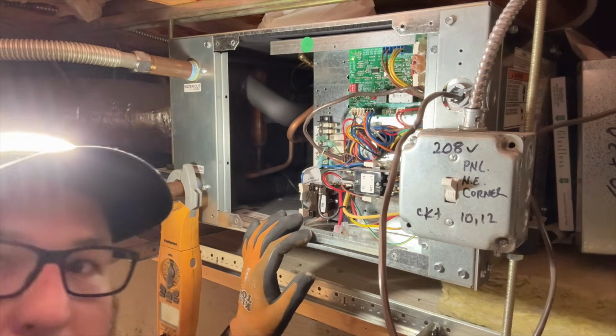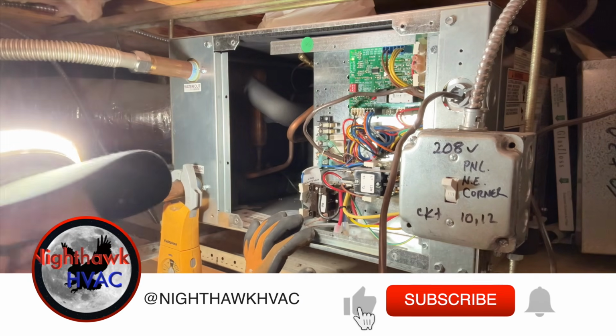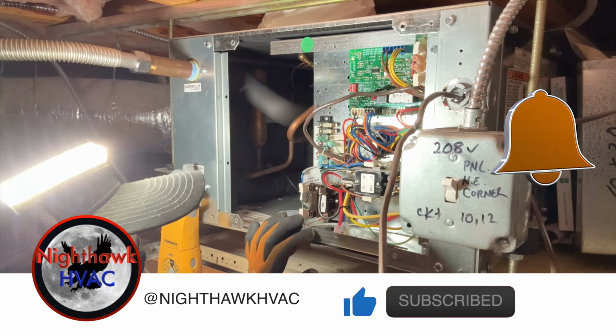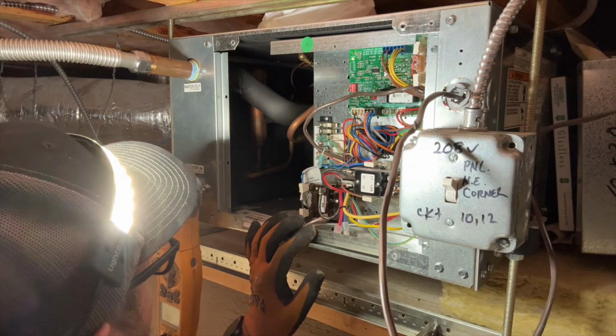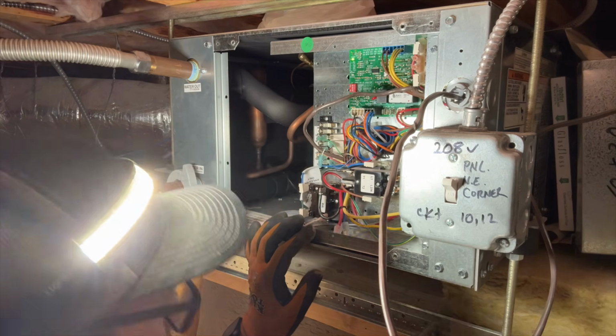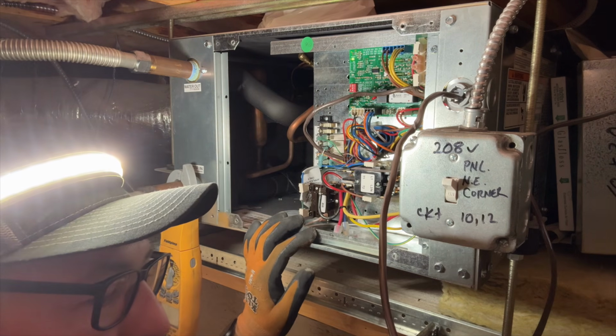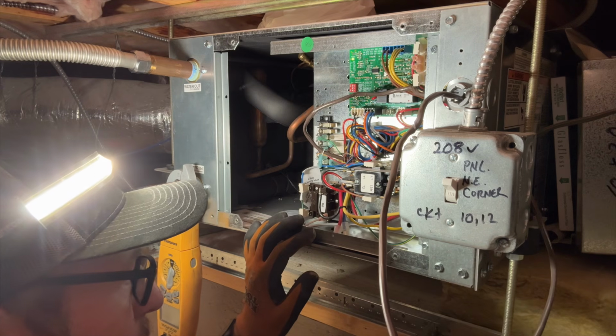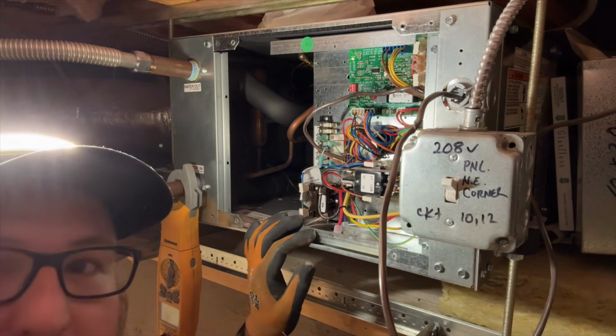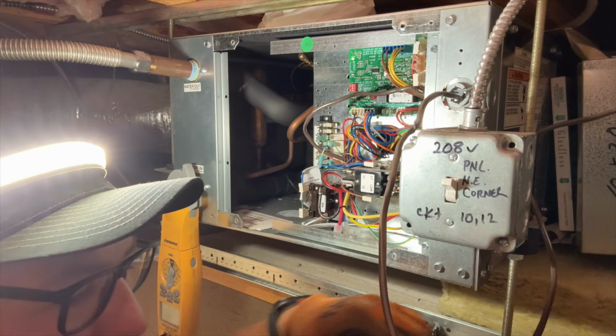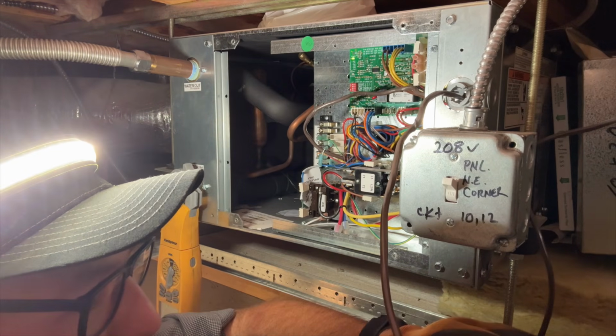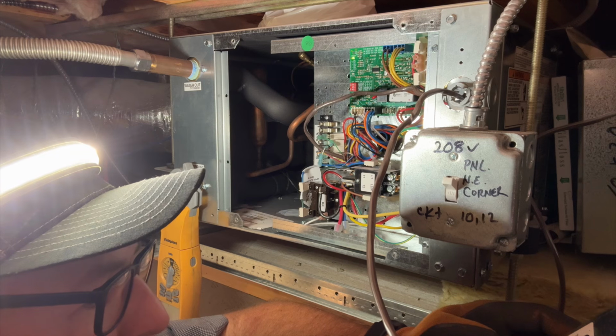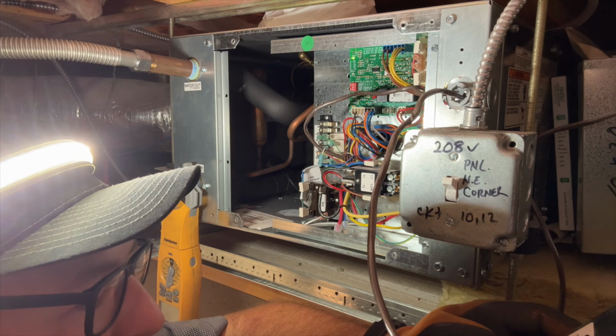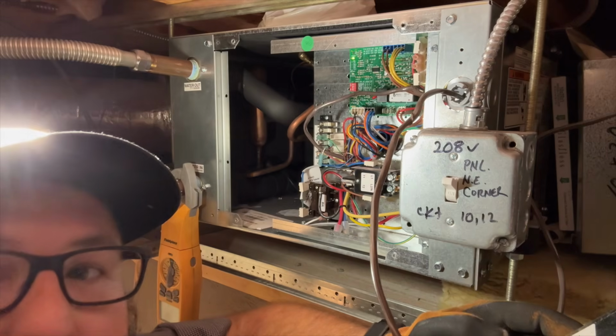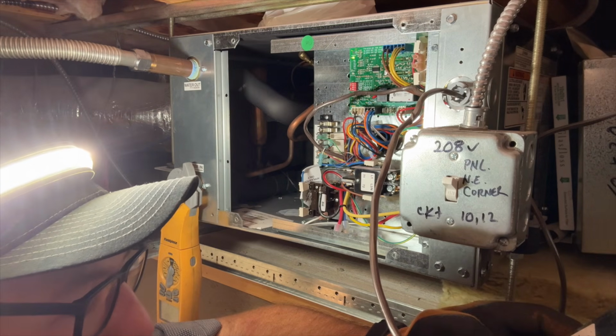Okay, so I've located the breaker. It is currently on right now. Basically, he's telling me that it trips, he resets it, and it's fine for a while, and then it randomly trips again. This one's actually one of the newer ones. It's from 2021, I believe, 2022, 410A. So we're probably overamping, so we're gonna check that. It is a 20 amp breaker. I am looking at this here. Minimum circuit for this is 6.7, max fuse is 15, so the breaker is a 20, probably a little too big.